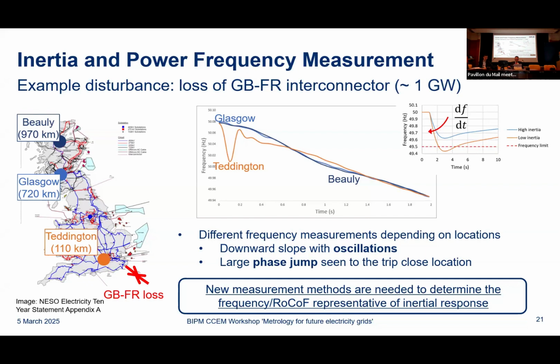But because we're replacing a lot of synchronous machines with power electronic converters, we've got decreasing inertia, and there's a higher risk of any type of frequency deviation for the frequency to fall faster, and it will also, for that reason, likely take longer to recover. So frequency deviations or frequency excursions are becoming a larger concern for that reason.